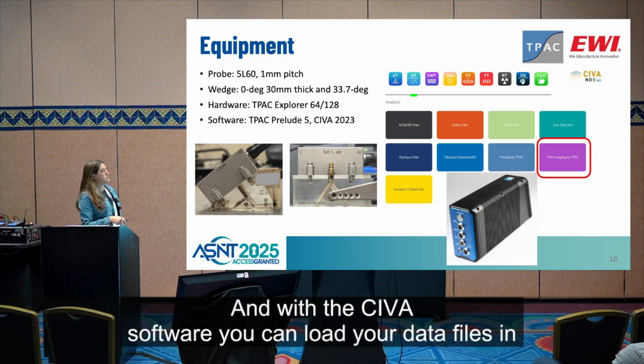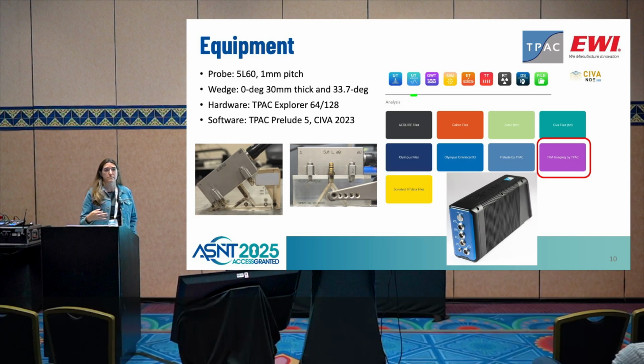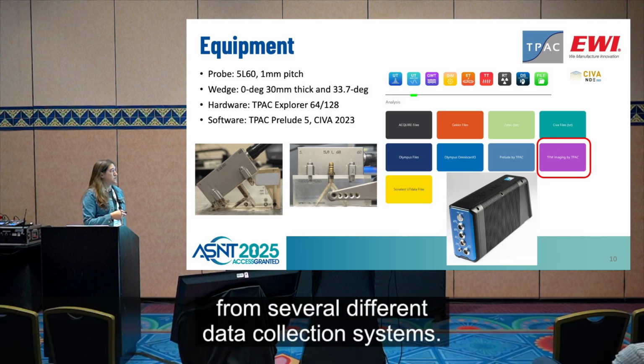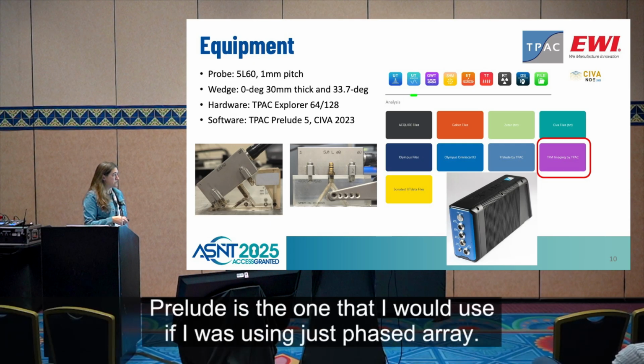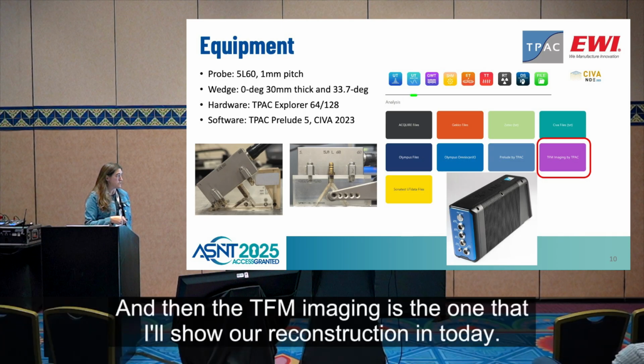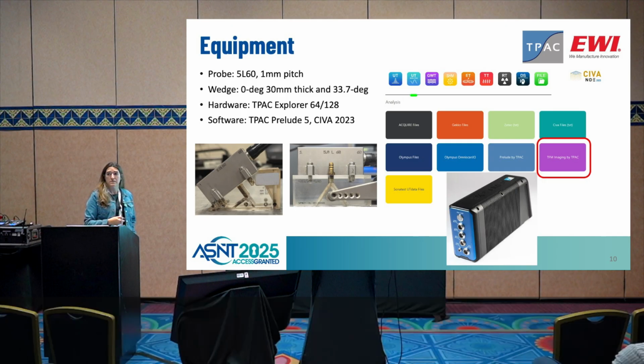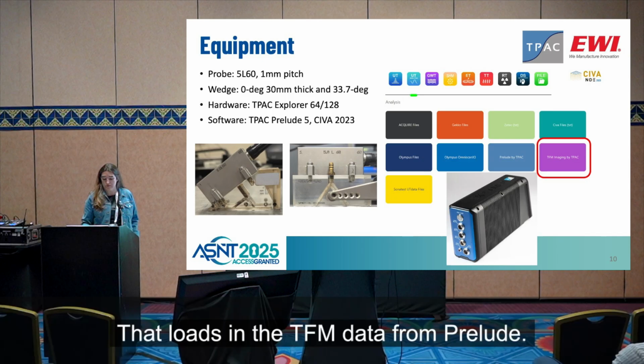And with the CIVA software, you can load your data files in from several different data collection systems. TPAC has a few in here. Prelude is the one that I would use if I was using just phased array. And then the TFM imaging is the one that I'll show our reconstruction in today. That loads in the TFM data from Prelude.